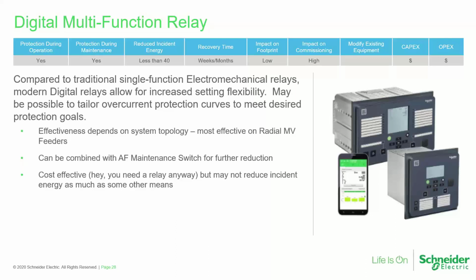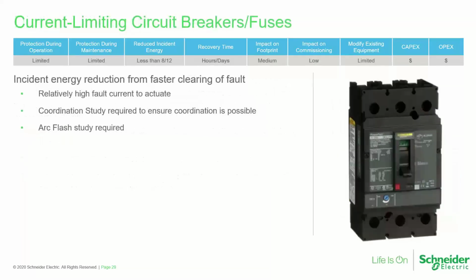But the capabilities of these relays also give you flexibility in terms of you can use sometimes arc flash maintenance switches with these other combining solutions. But even by itself, just the digital multifunction relay may get you well below that 40 calorie per centimeter squared threshold if that's what you're aiming for. So just make sure that you're not using things that are so simple that you miss out on some of the flexibility that you can get with a little bit more advanced solution.